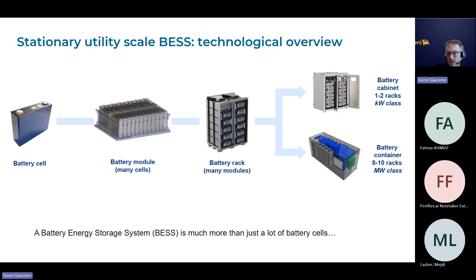If you want to use them, you need to consider that you don't have only the batteries. The batteries come together with what is called the BMS, the battery management system - the electronic board that controls and monitors the battery to avoid overheating, overvoltage, undervoltage, and all the safety issues that can come with a bare battery. You cannot communicate directly with the battery; the manufacturer will always provide it together with the battery management system. In a battery management system you could have different providers - you don't necessarily have a single provider of the overall energy storage system.